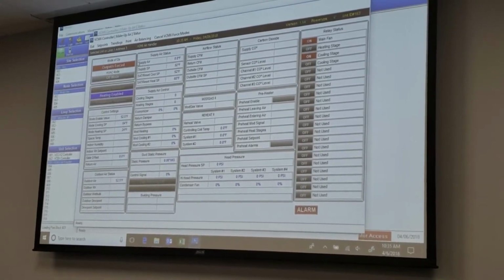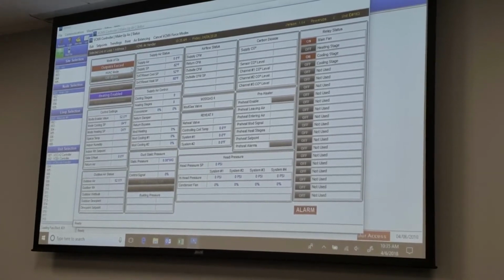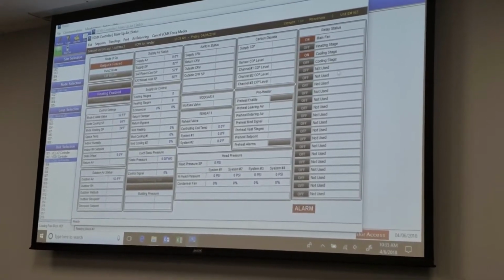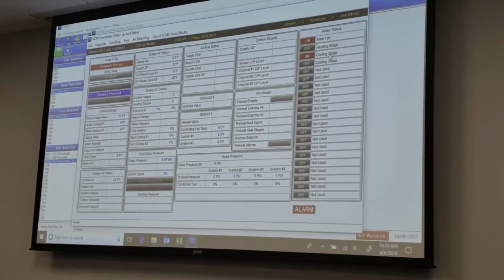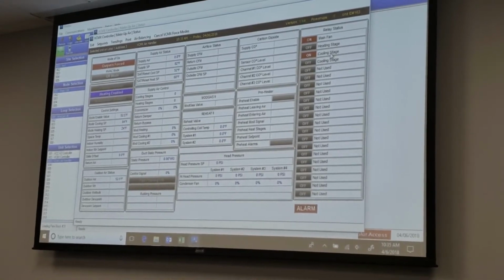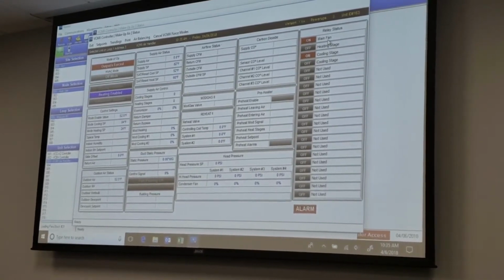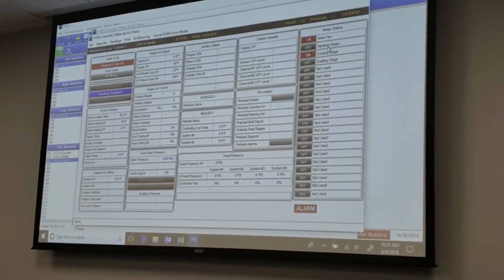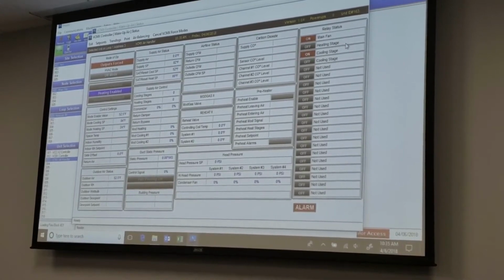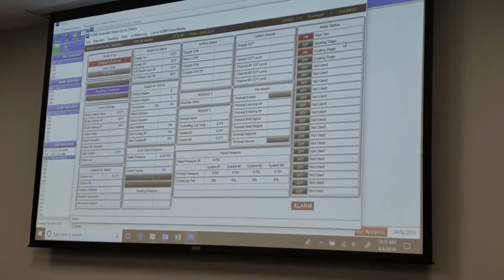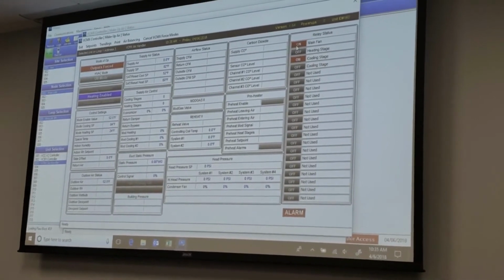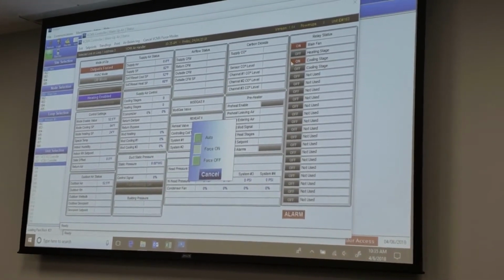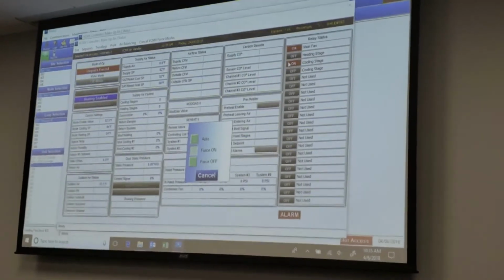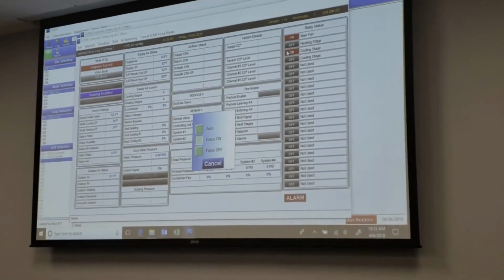So I got force relay. My outputs are forced, so it tells me that I'm forcing something, and it tells me which relays are forced. Anything that's lit up in red is forced. Anything that's green, it's being told to turn on. Anything grayed out is off. So I can actually go in there, force them on and off. Are they time sensitive? When you force them, 2 hours? 2 hours. They'll stay on for 2 hours for us.